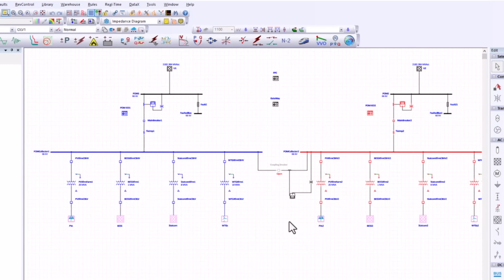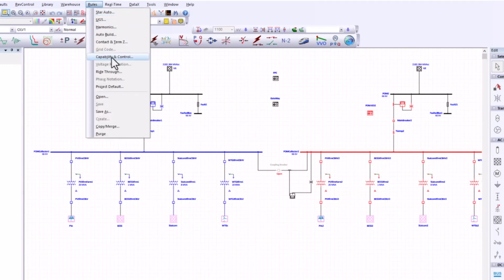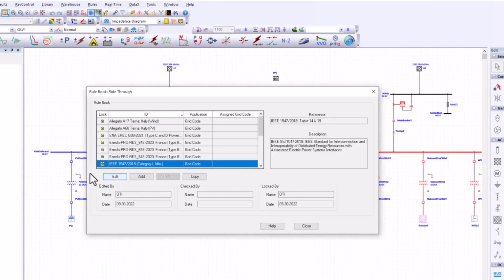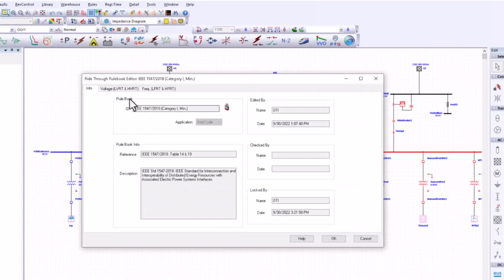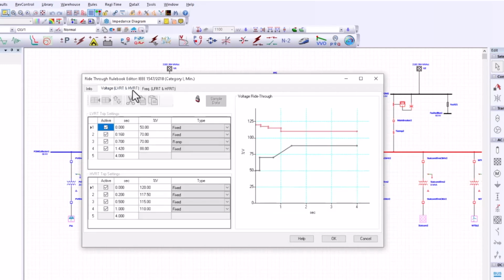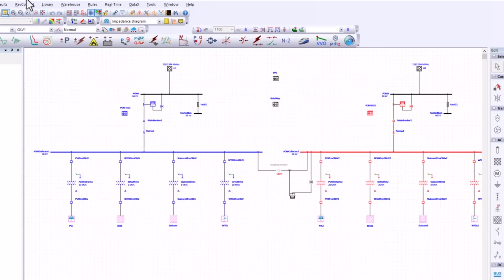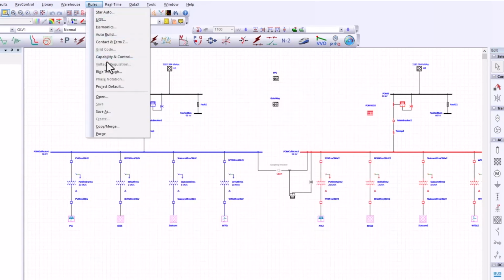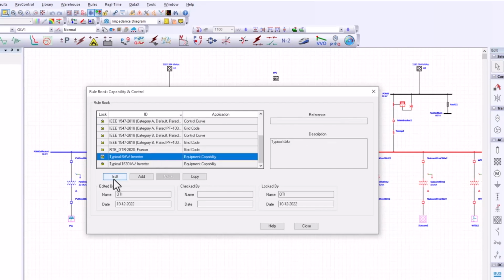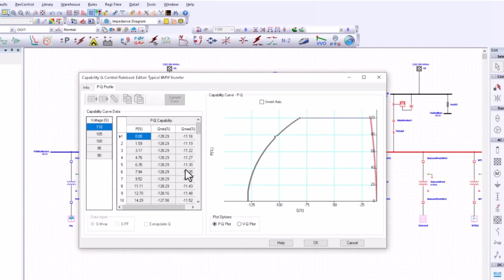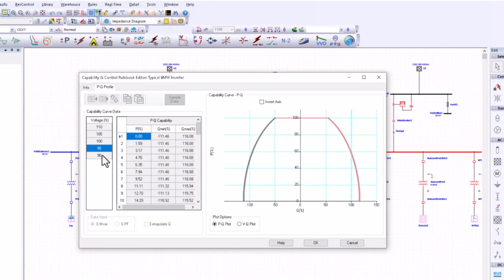ETAP offers several powerful tools to assist with modeling. For example, if you need to verify compliance with the grid code requirement, you can define these requirements in the rulebook. You can find rulebooks under rules in capability and control, and different items are available here. ETAP allows you to use a predefined rule or create custom ones. For example, this is an example of a rulebook that we have for ride-through capability for LVRT, HVRT, LFRT, HFRT. Or you can also specify the equipment capabilities that you have for your inverters and other assets that you have in your system. Here's another built-in example that is available in ETAP. But you can define your own capability and grid code requirements in the rulebook as well.